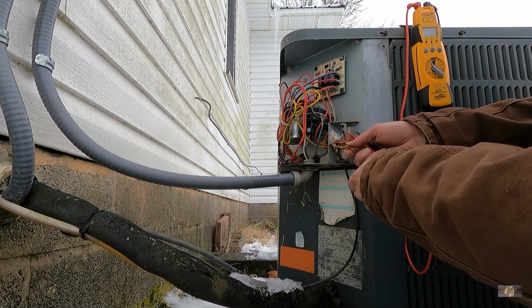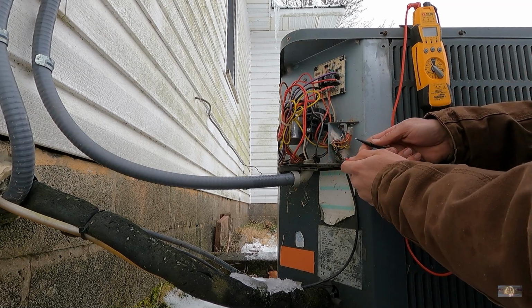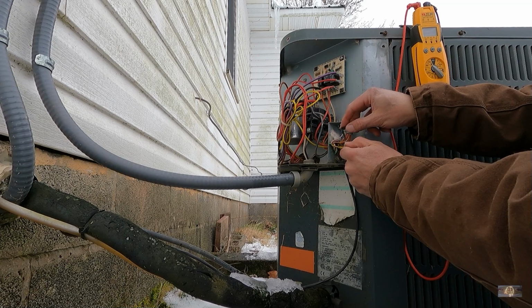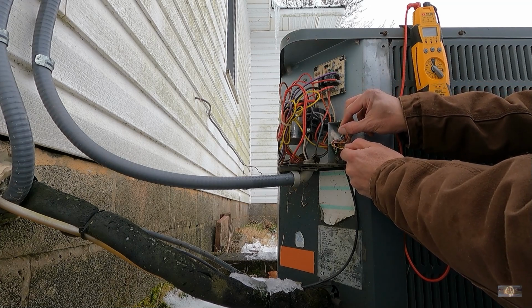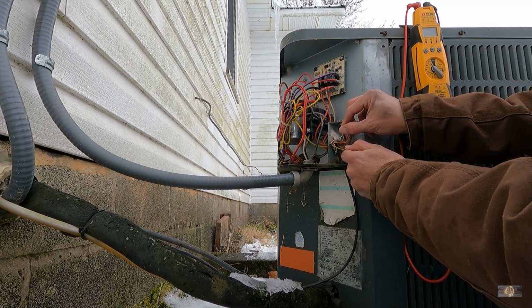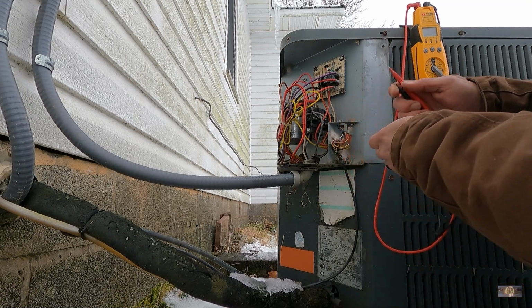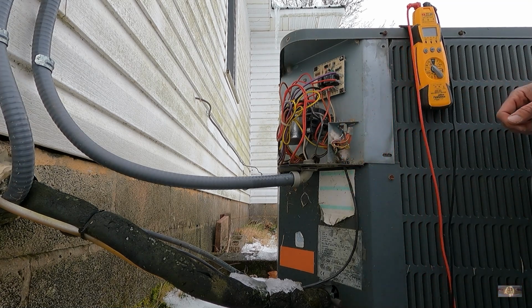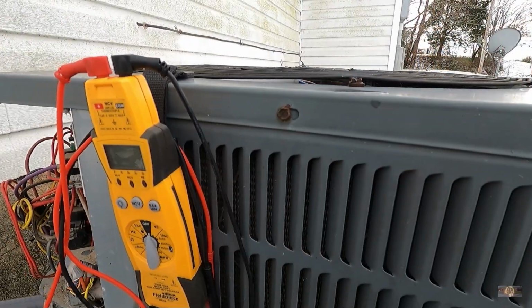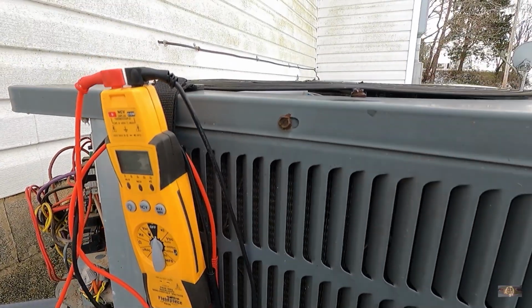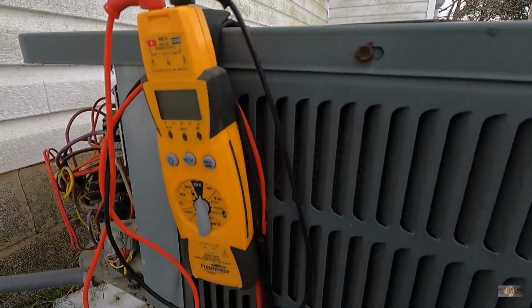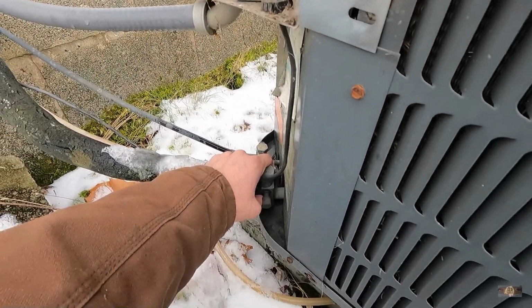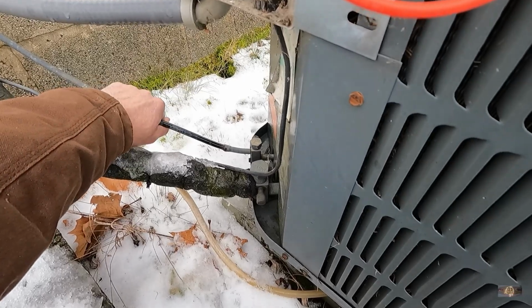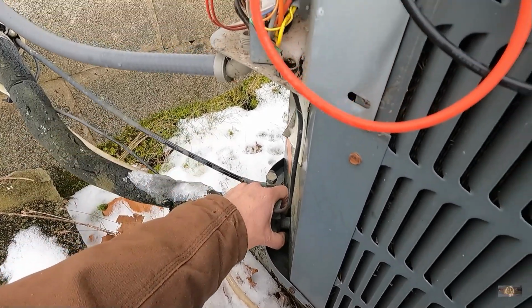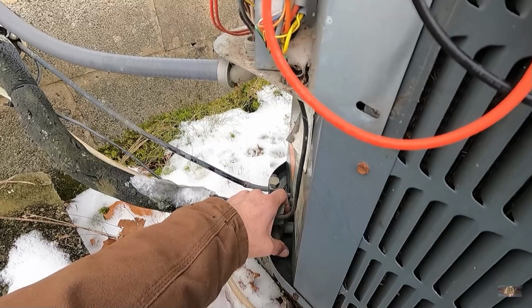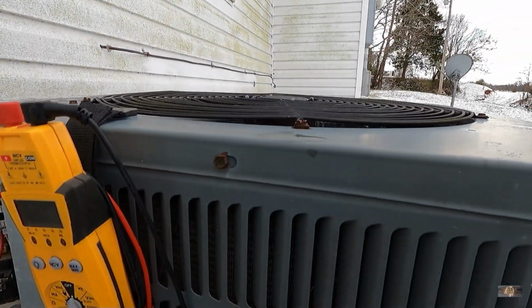The buggers are tight. Alright, I'm just going to check C to Y here. Yeah, I don't have a call out here for heat right now. Nothing. Alright, I'm going to have to go see if she accidentally power cycled and we're in time delay. No sooner than I went inside, the dang thing started. But I just came around here and I don't hear a compressor running. Feels like that line's warm. No noise right now. Fan's running smooth.